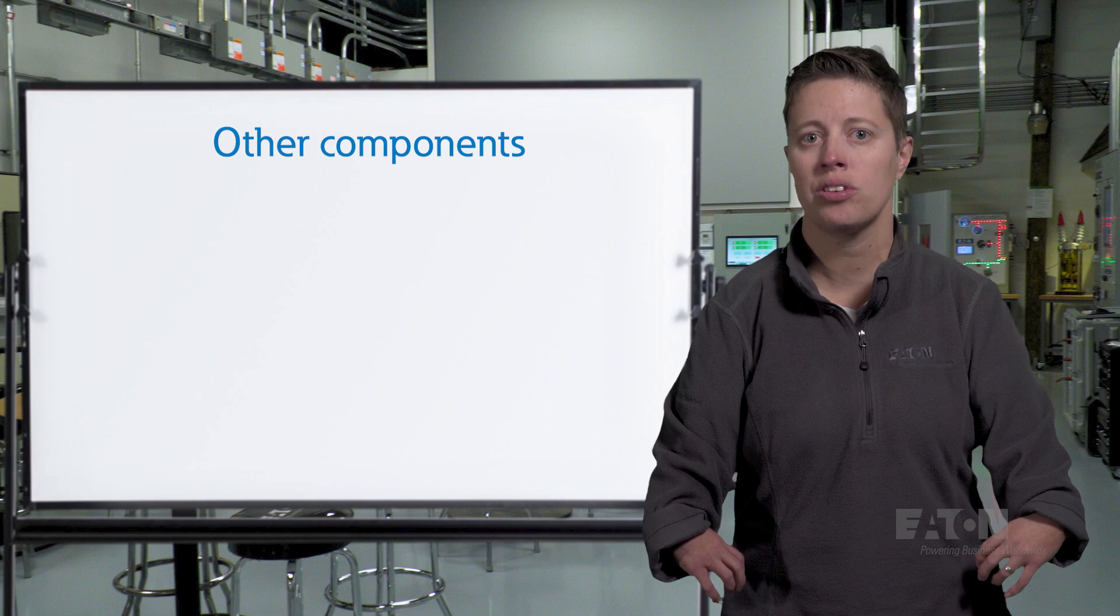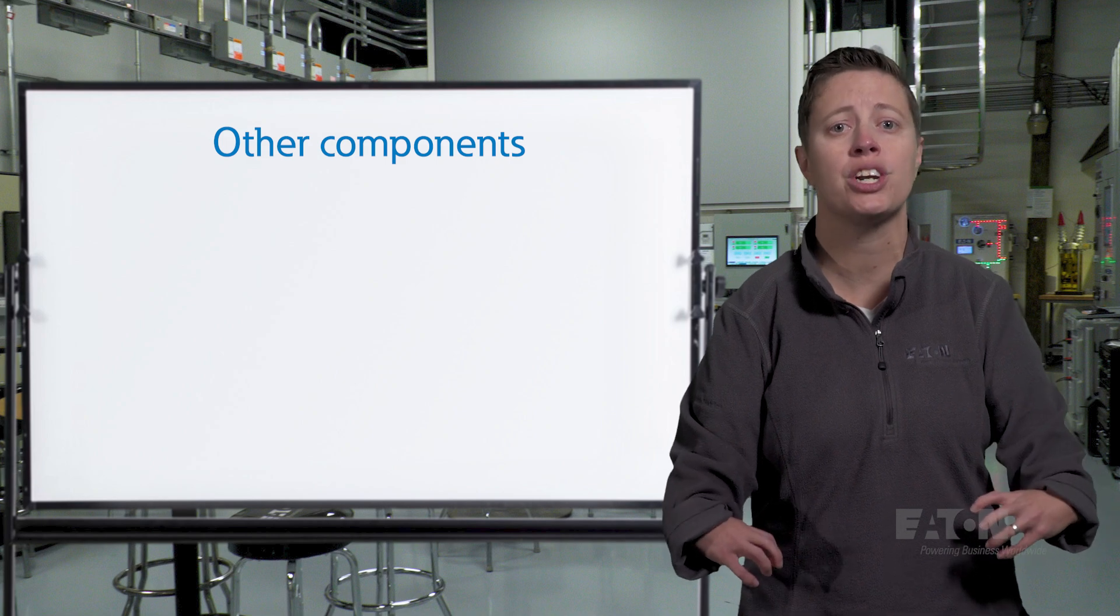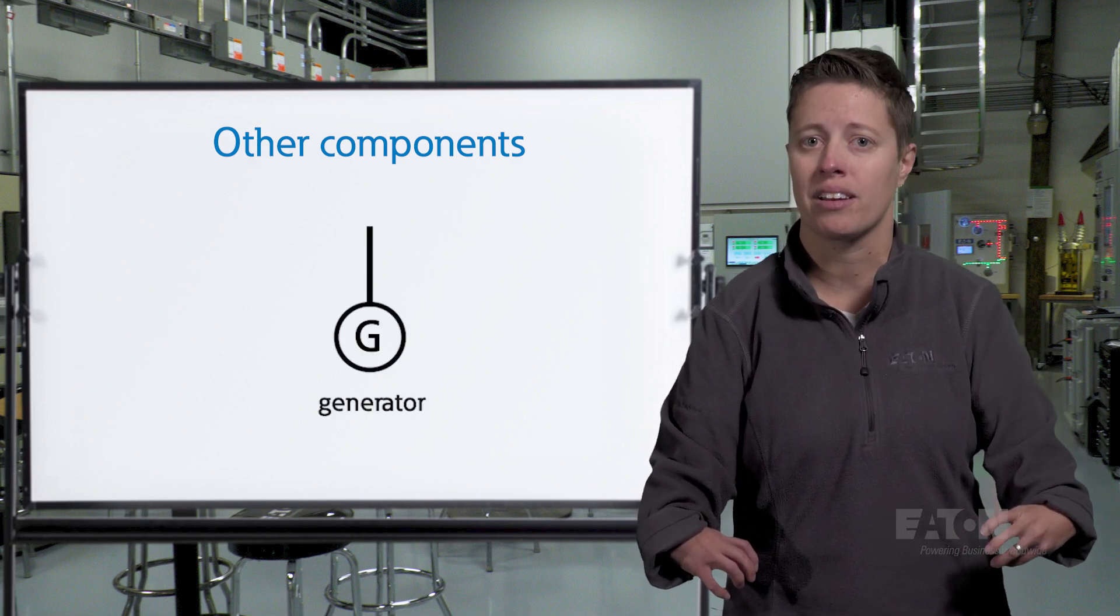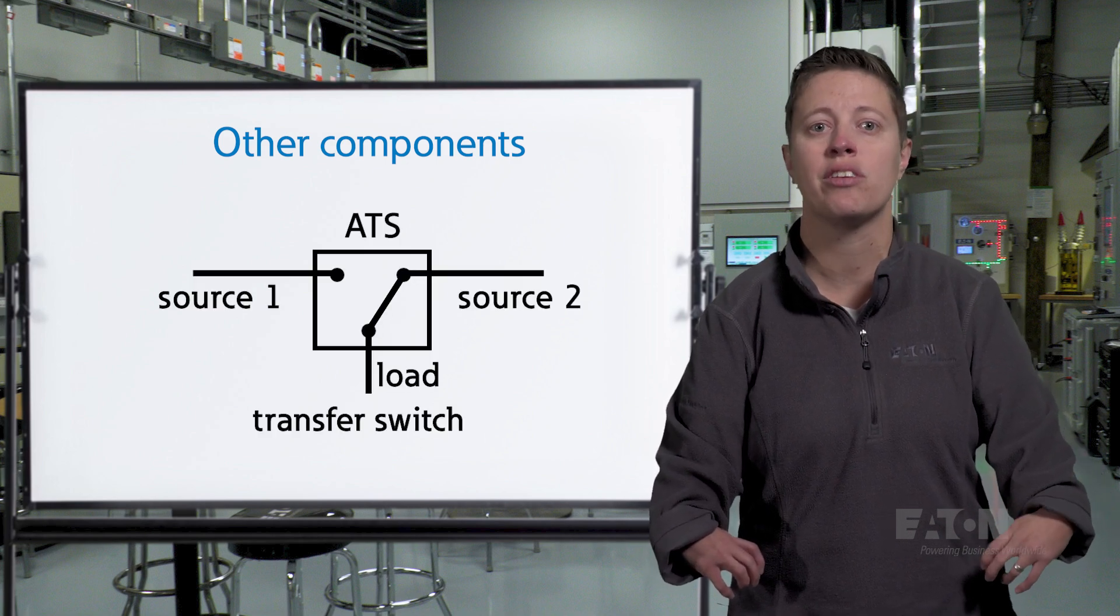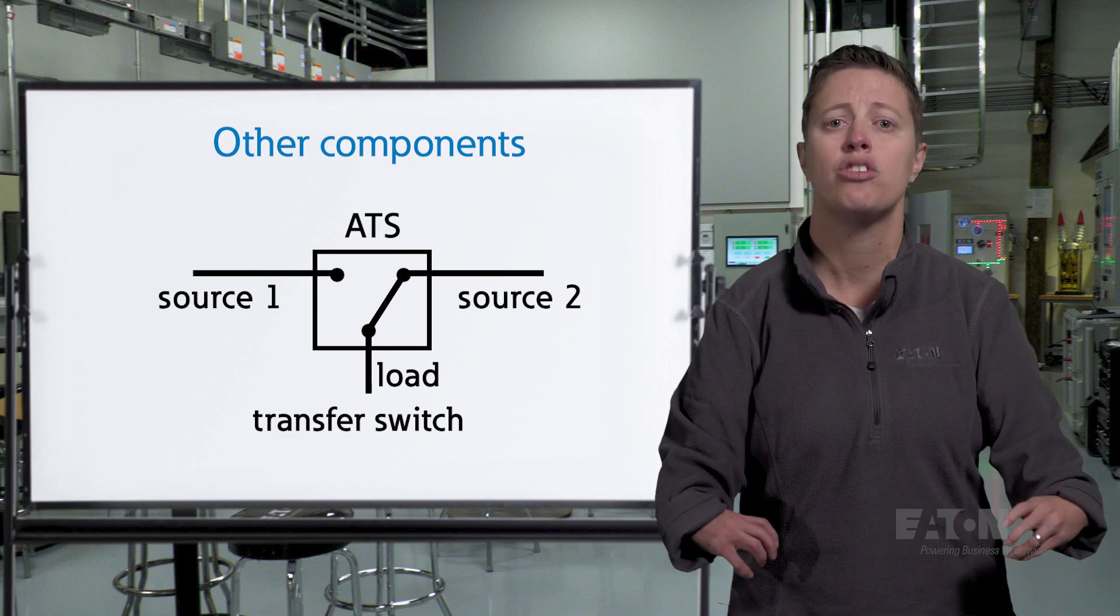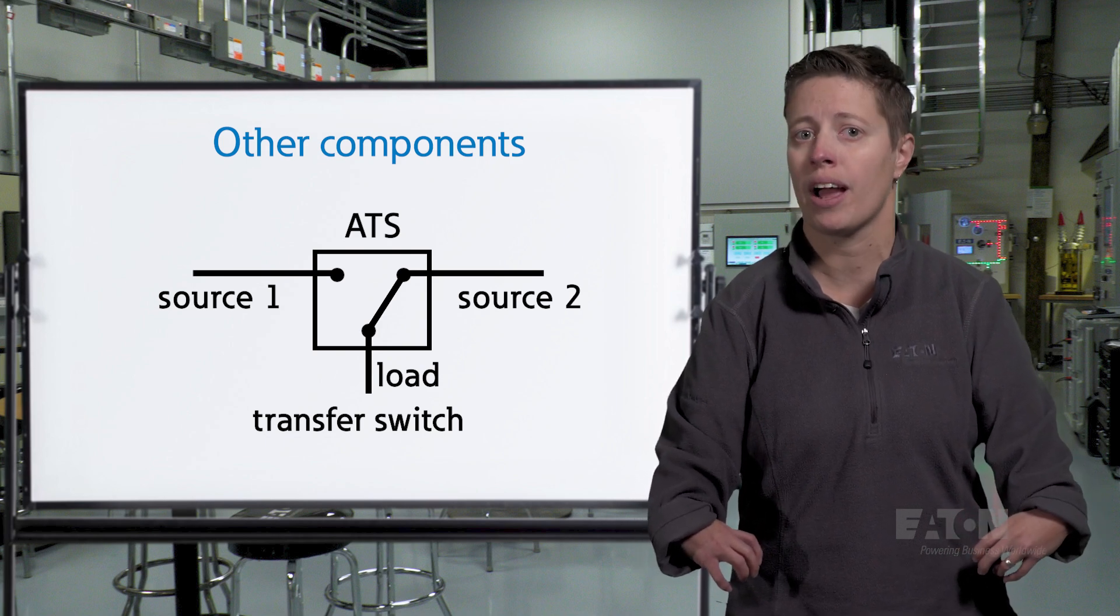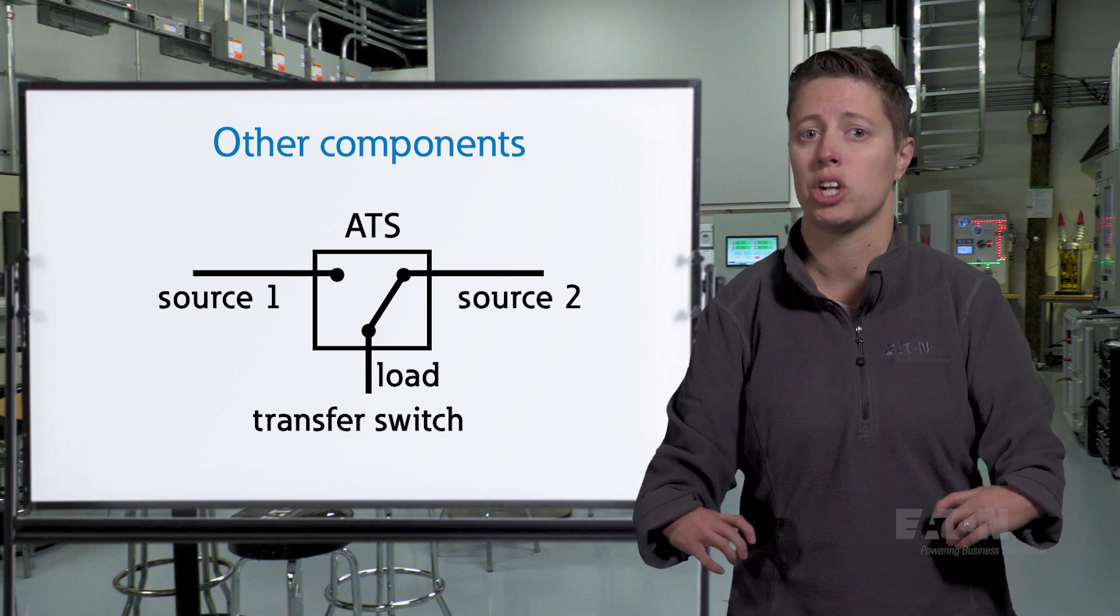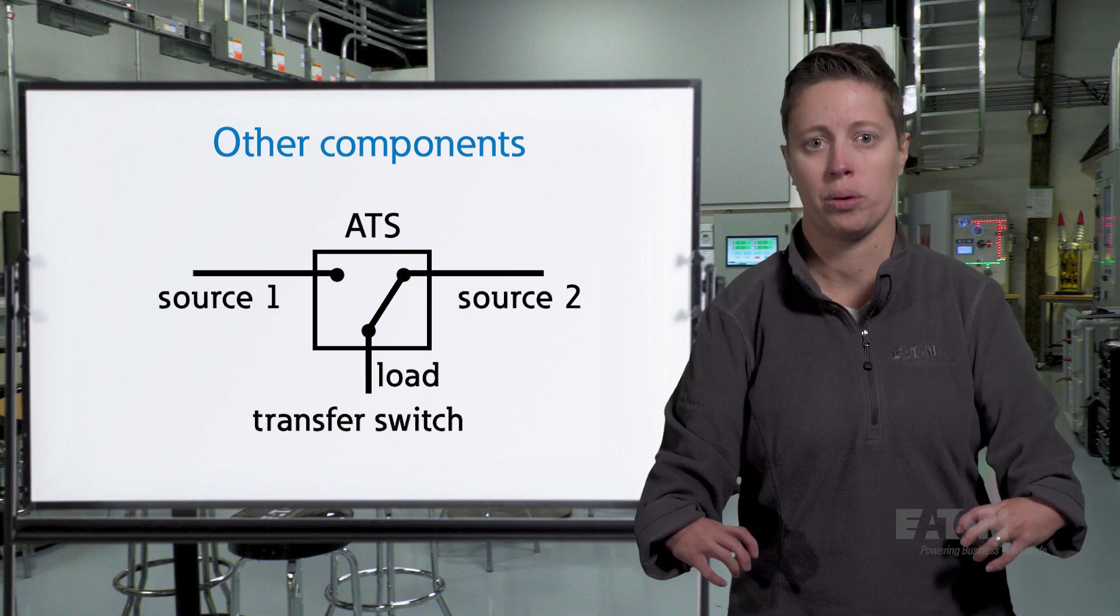In addition to utility sources, it is important single lines also show both permanent generators and provisions for temporary generator hookup. Generators are usually depicted as a circle with a G inside. The transfer switch symbol indicates a device used to switch the power supply from one source to another, often to and from a utility source and a generator source. It is typically shown as a rectangle with two inputs and one output, and lines indicating the switching action. It is likely to be labeled ATS for automatic transfer switch.